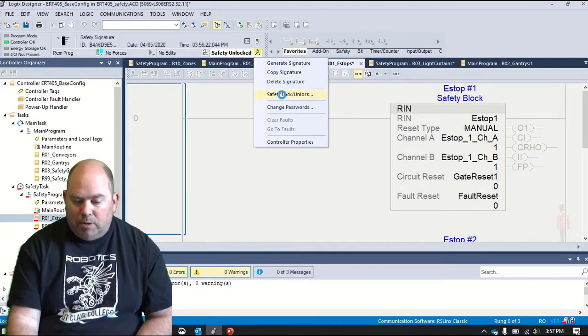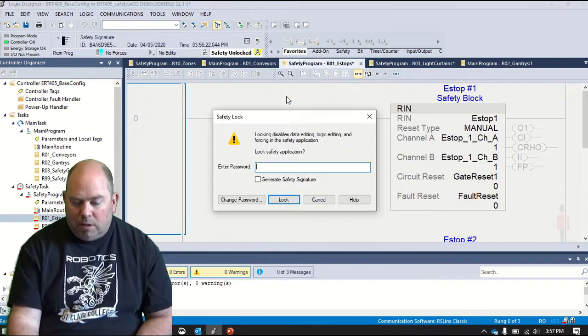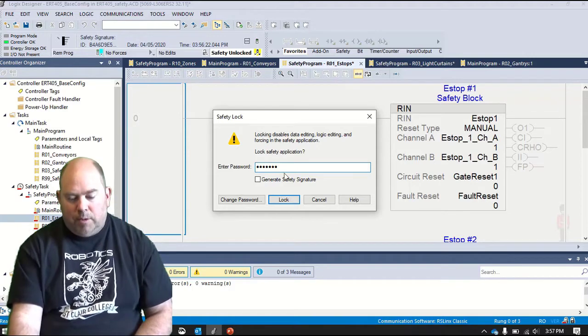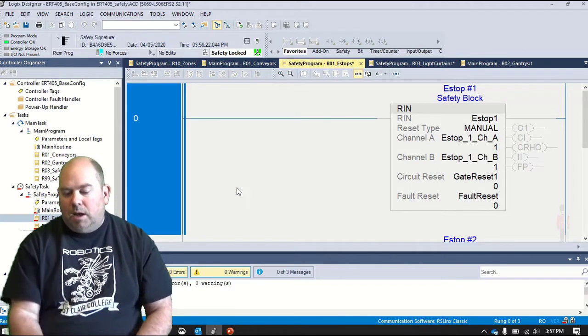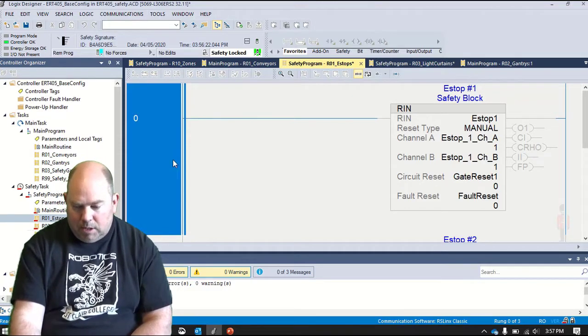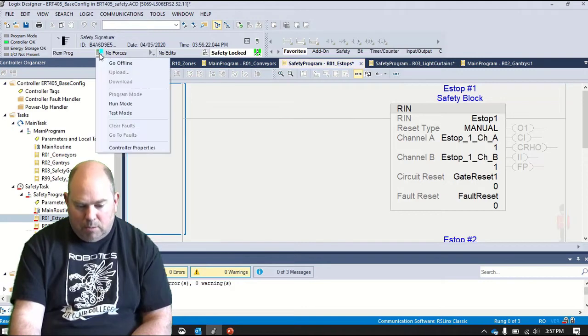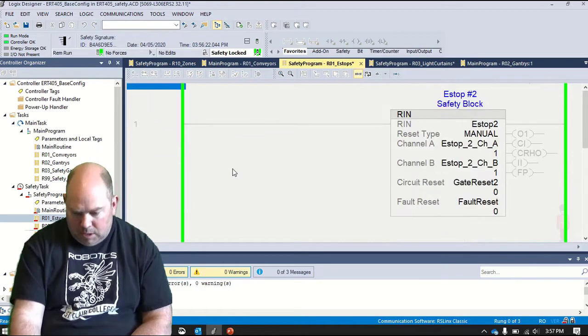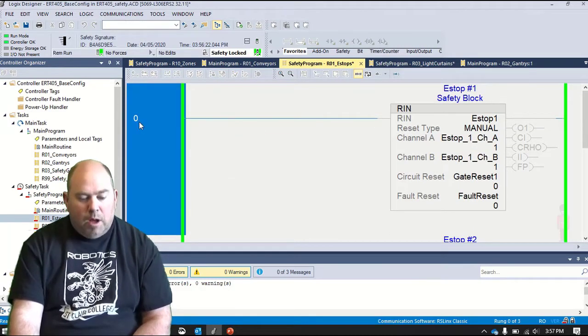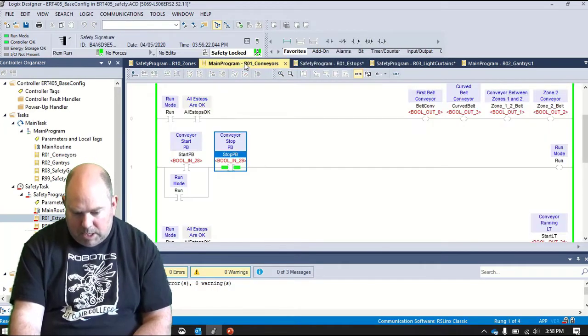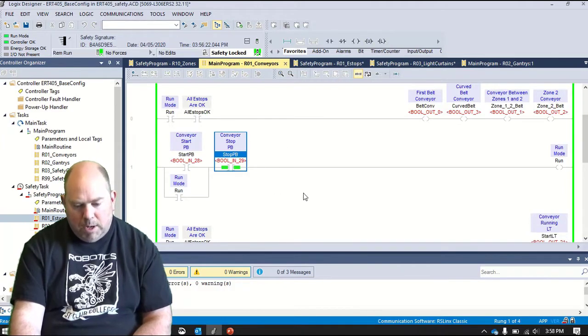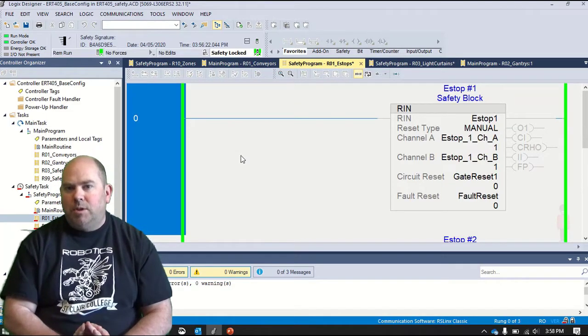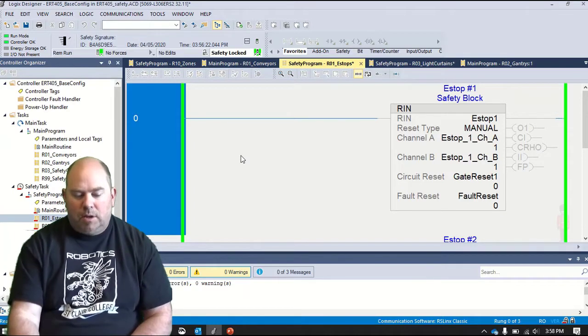So now what I'm going to do is lock this system. So I need to put in the password. So I've created a password for this. And now I'm going to lock it. Now you will notice here that once I lock this and go back into run mode, this logic, and it's difficult to see on this screen, but this logic is all gray. If we look at the main program, the standard logic, this has a nice white background. Safety logic all now has a gray background. Anytime you see gray background logic, that means this is logic you cannot edit.